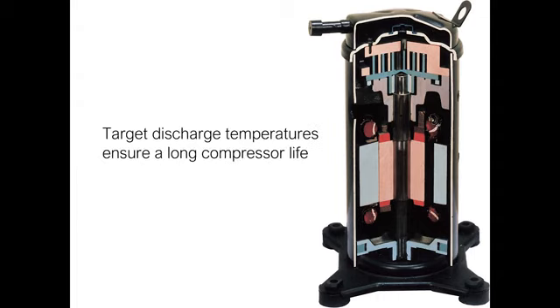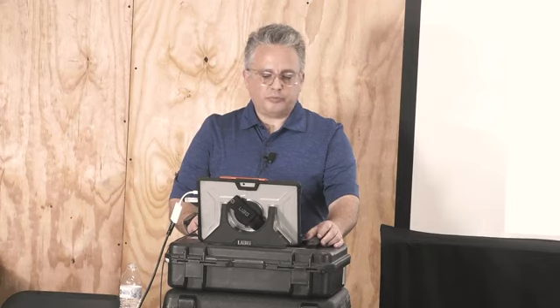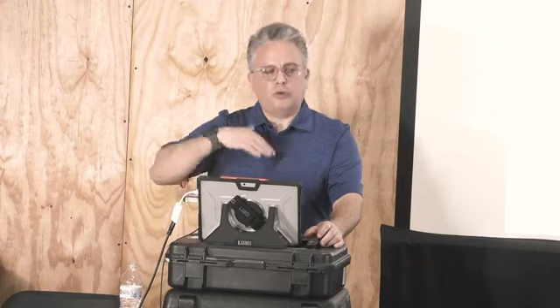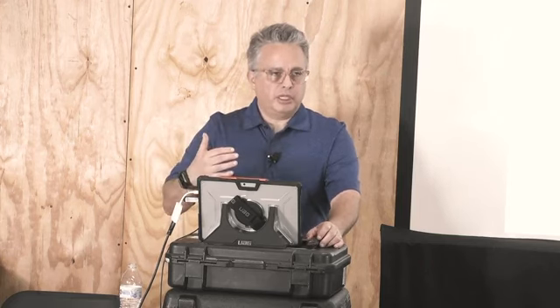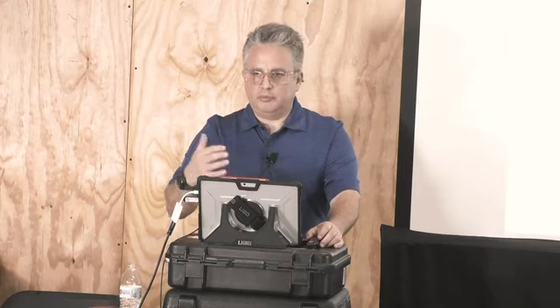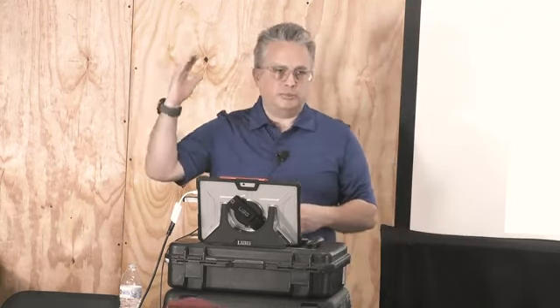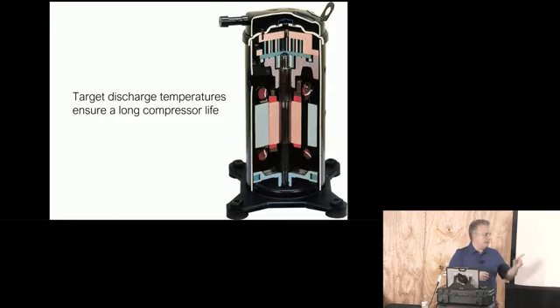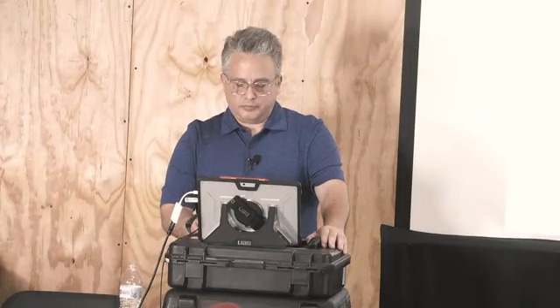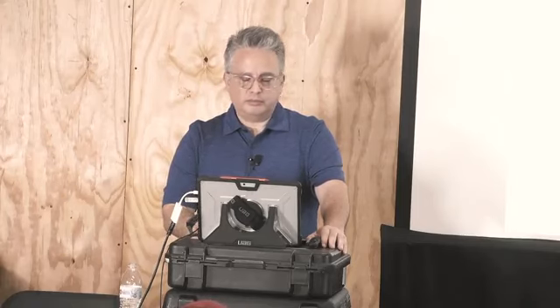So with the target discharge temperatures, they ensure that the compressor has a long life, right? Because it seems to me that if all the refrigerant components, proper installation, maintenance and refrigerant charging of any particular refrigeration system, whether it's a water cooler or a 10,000-a-day industrial ice machine, are to spec, the compressor is happy. And so one of the ways to discover the compressor's operating performance is managing and understanding the target discharge temperatures for that particular design. So that's where that Dallas story of this hotel came to mind.